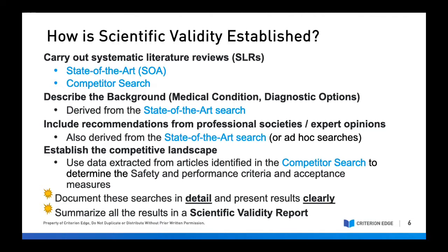But suppose your IVD is designed to detect a novel analyte, or if there's limited evidence regarding your analyte in published literature. In this case, you may need to rethink the strategy necessary to establish your scientific validity. But this is why it's recommended that you begin this scoping process very early in your PER preparations, because limited data supporting scientific validity will significantly impact the quality of your PER as a whole.